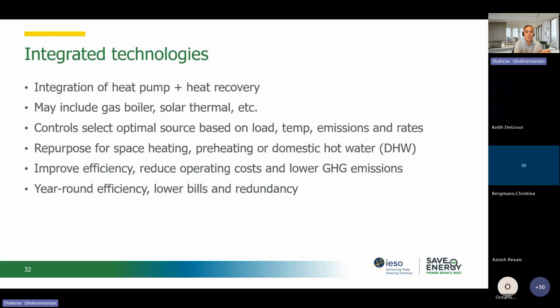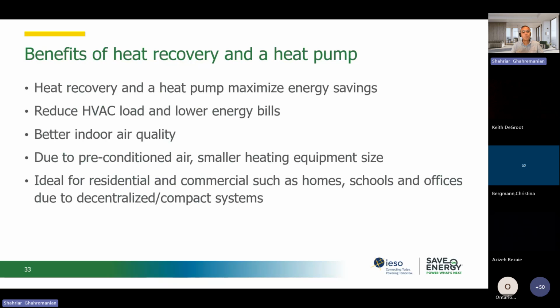The proper control, as we discussed, can be based on the load, the temperature, emissions, or the rate that we have. And then we can repurpose the space heating and use the extra waste heat for preheating domestic hot water, and so on. What is the outcome of integrating these two? Increasing the efficiency, reducing the operating costs, lowering the GHG emissions, and we are going to have year-round efficiency, lower utility bills, and better redundancy in our system. One thing to consider is that if we integrate these two, our equipment size will also go down, meaning we need a smaller size, which equals less capital cost.